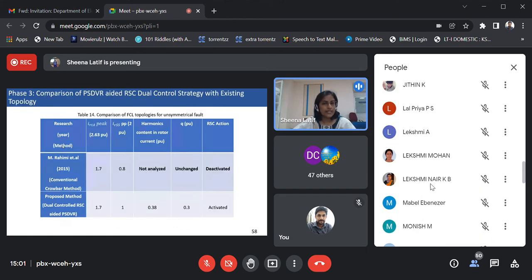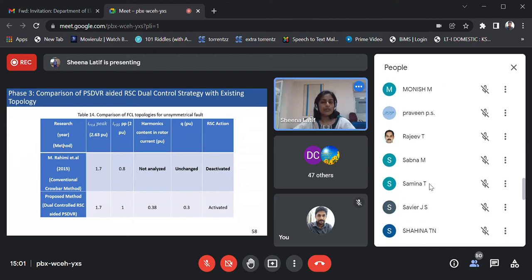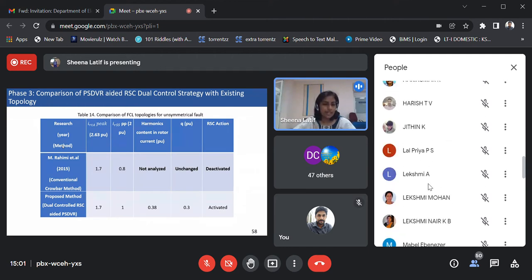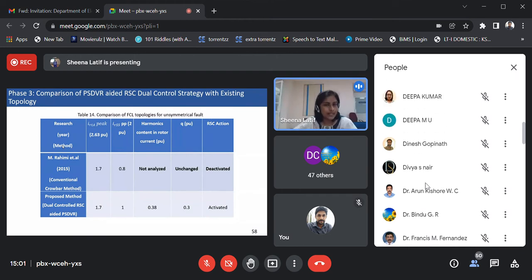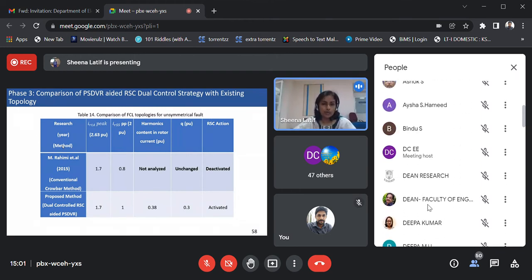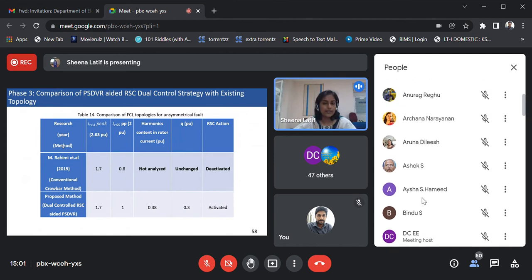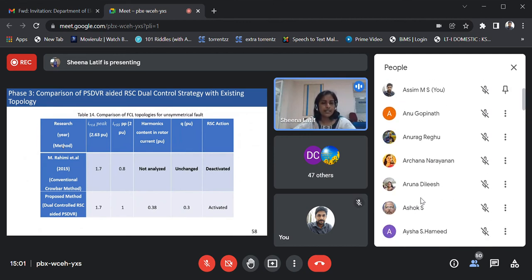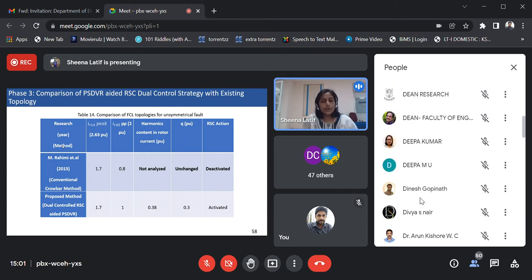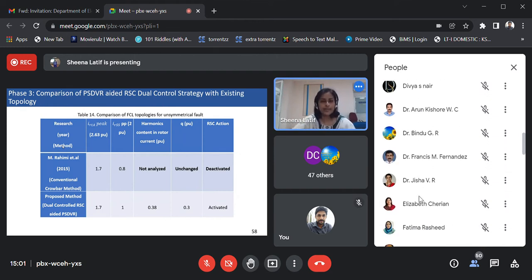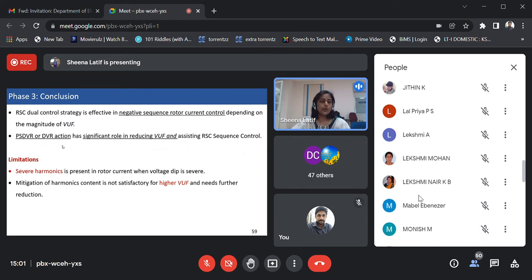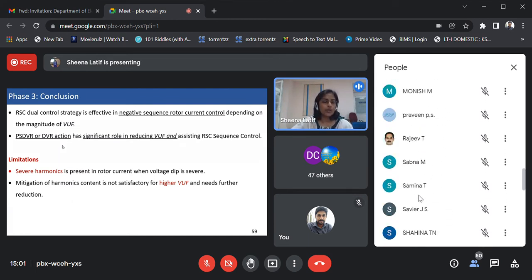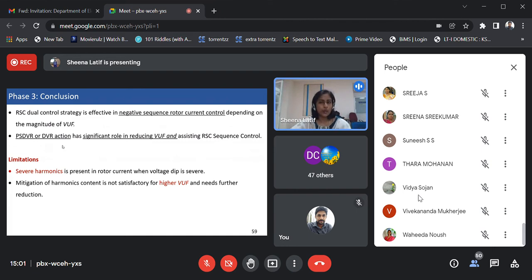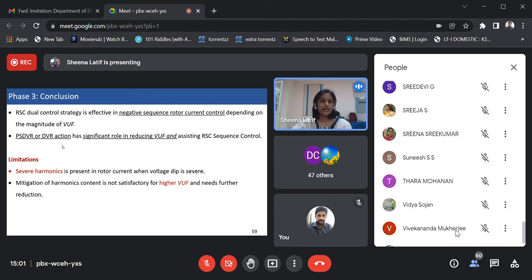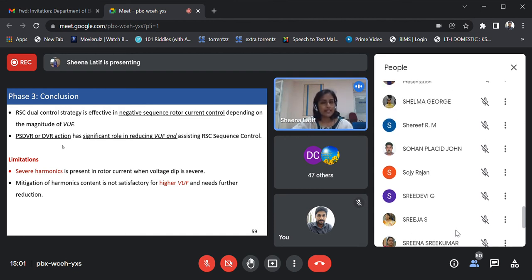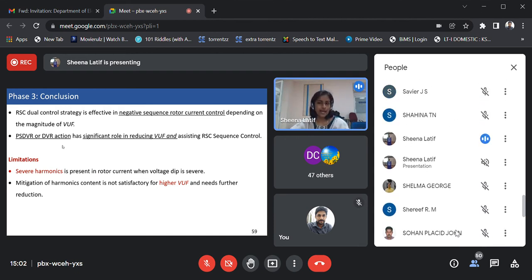The proposed PSDVR aided RSC dual control strategy for a double line to ground fault is compared with the conventional crowbar method. We can see the transient component rotor current reduction is almost comparable with the crowbar method, and the steady state rotor current reduction is also similar, while we do not need RSC deactivation during this period. So as a conclusion of this phase, the RSC dual control strategy is effective in negative sequence rotor current control if it is not reaching its saturation condition, and the PSDVR or DVR has a significant role in reducing the VUF and assisting the RSC sequence control.